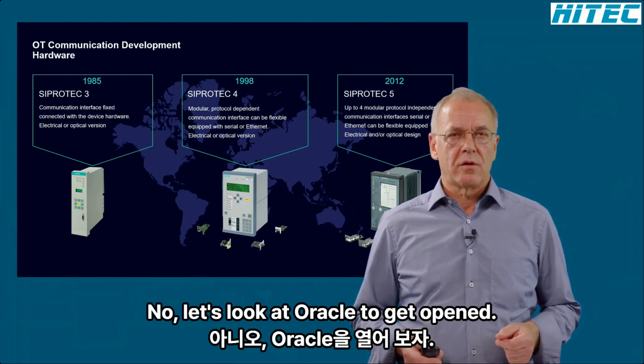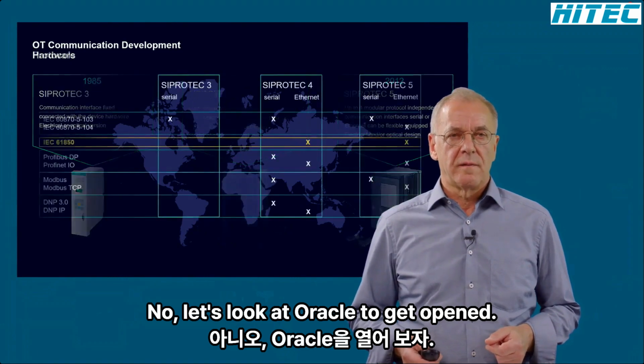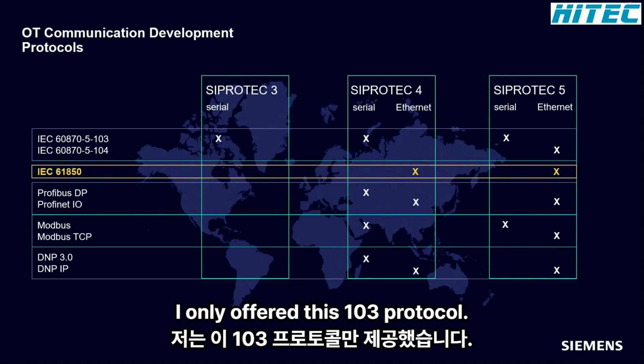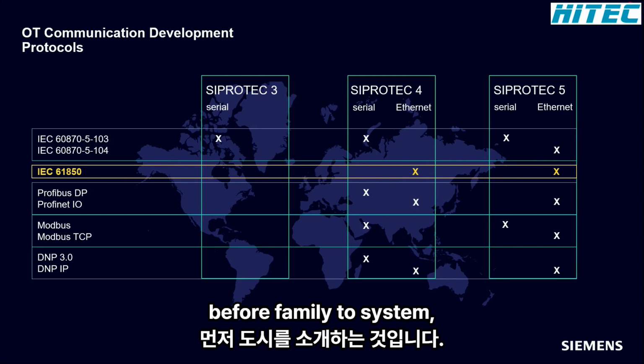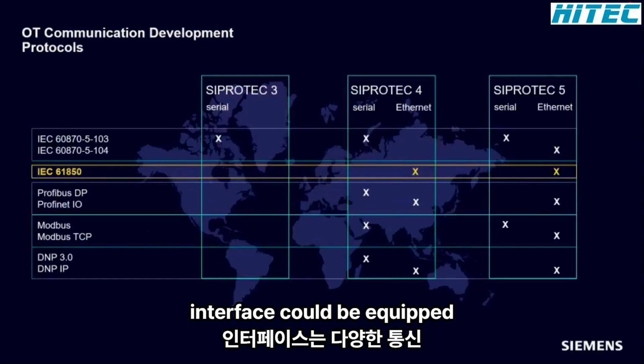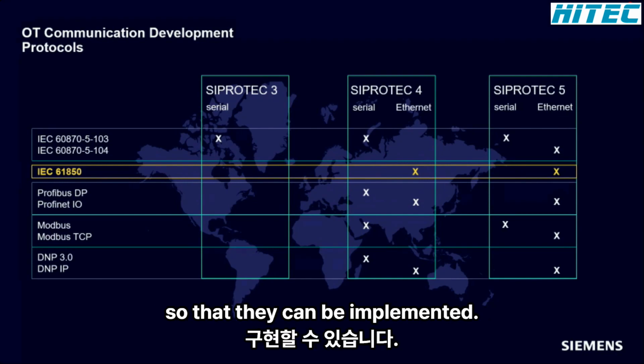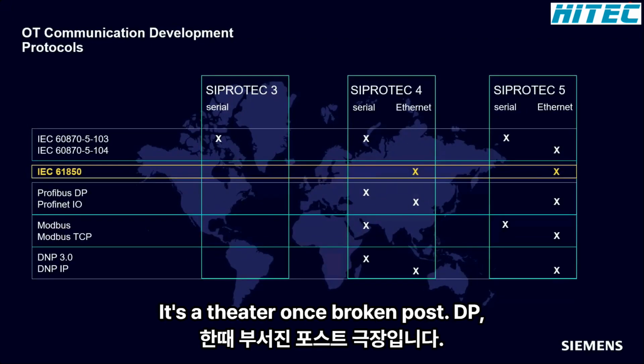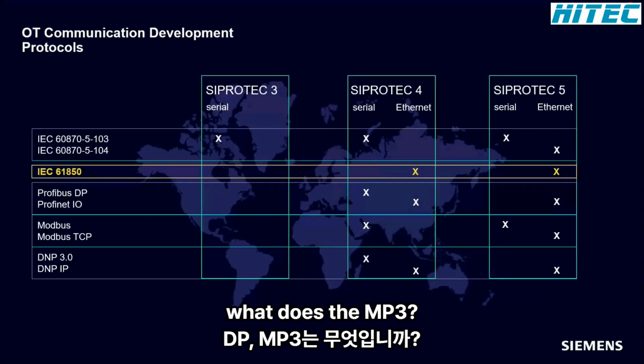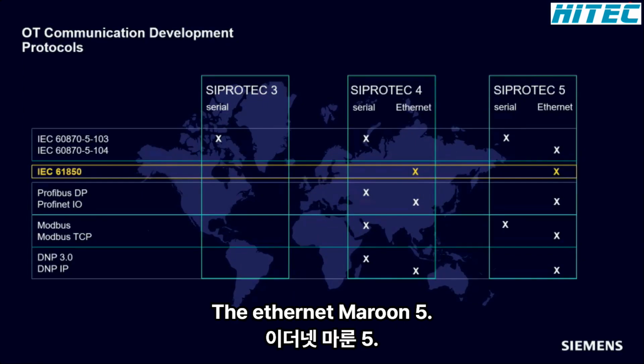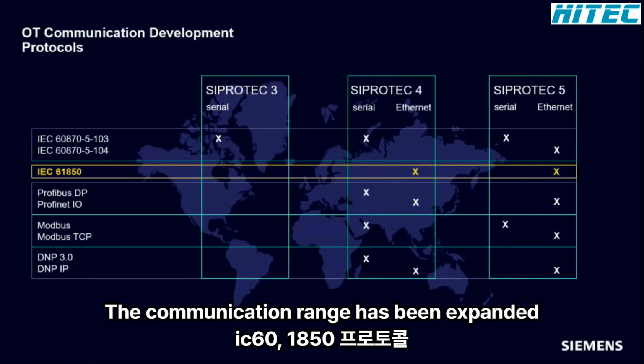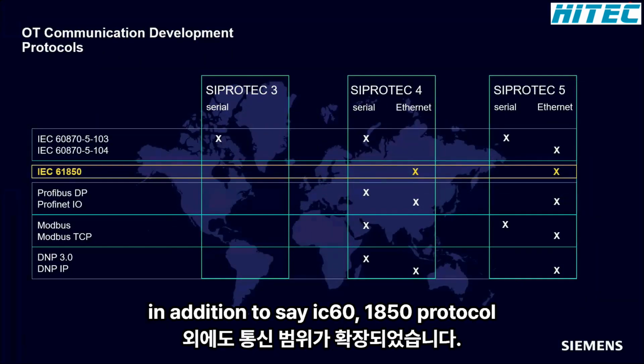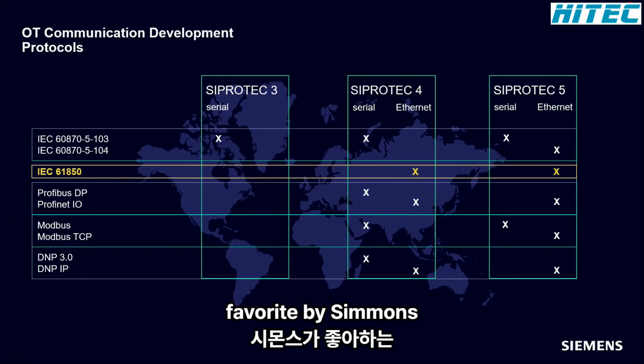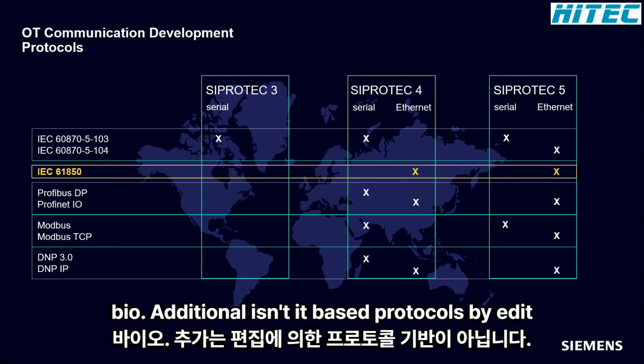Now, let's look at protocol development. The SIPROTEC 3 devices were only offered with the 103 protocol. With the introduction of the SIPROTEC 4 family, the system interface could be equipped with various communication modules, so that further additional protocols could be implemented, with the serial ones Profibus DP, Modbus, DNP3. On the Ethernet module side, the communication range has been expanded in addition to the IEC 61850 protocol favored by Siemens, with Profinet IO, DNP IP.